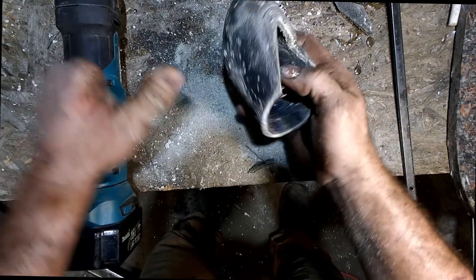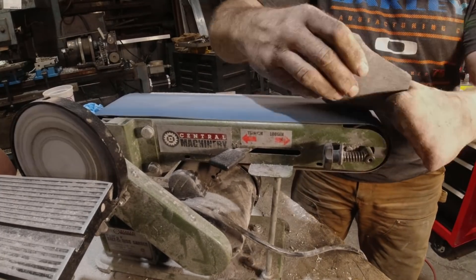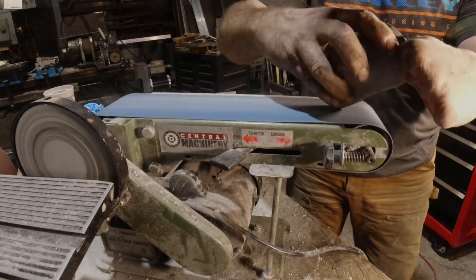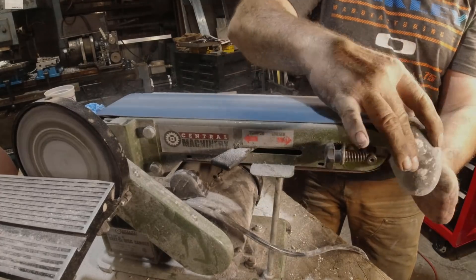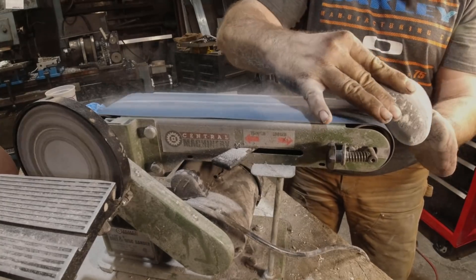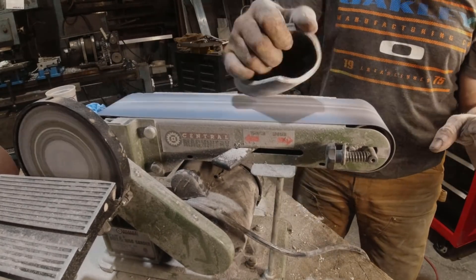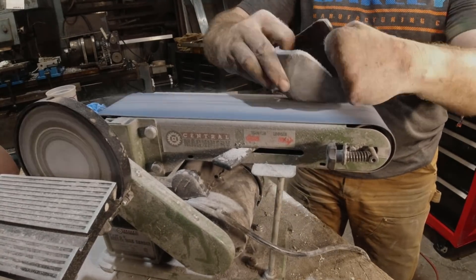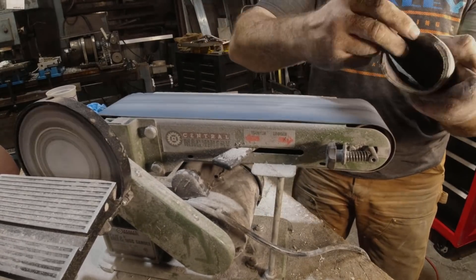Once you can fit your hand into the socket and nothing seems to be biting you, it's time to turn to the belt sander and start sanding it to its final shape. I'm using a 60-grit zirconium belt for the roughing operation. Be sure to go back and forth between sanding and fitting to get the socket where it fits really well on your residual limb. Trim the back of the wrist so you can move your wrist forward and back without anything biting you. You have two layers of black socks that you can sand to get everything to an even level. If you start seeing the yellow layer, stop and add another couple of layers of socks to the outside — you want the socket to be about five layers thick; that's where the strength comes from.